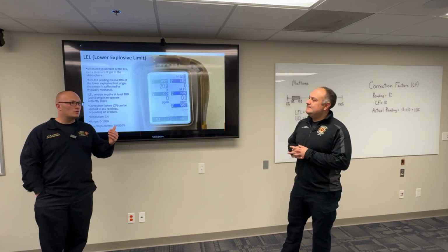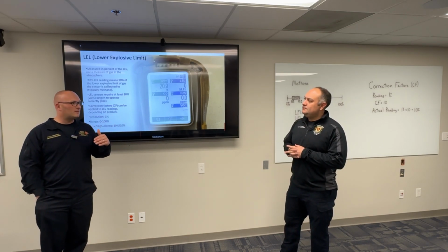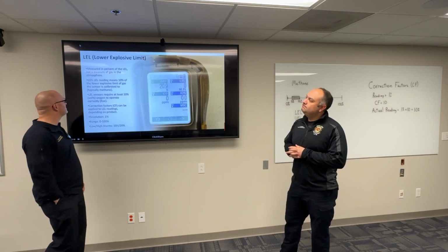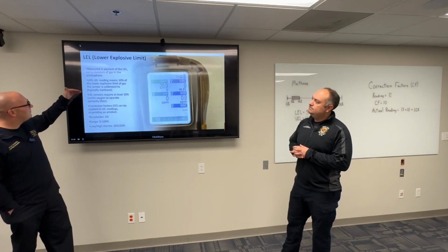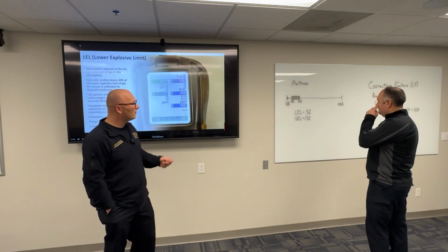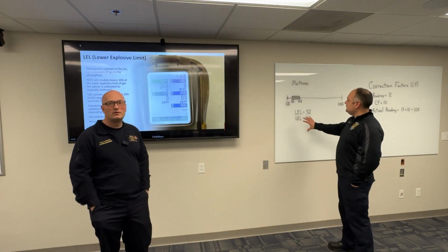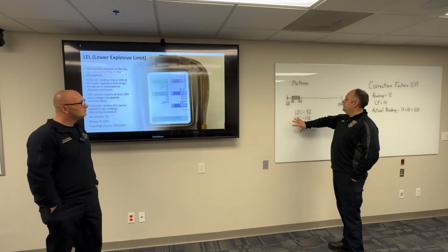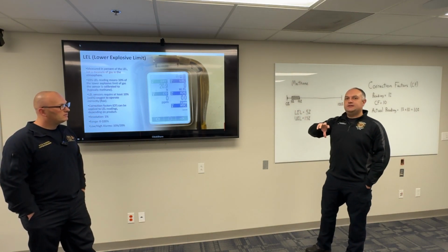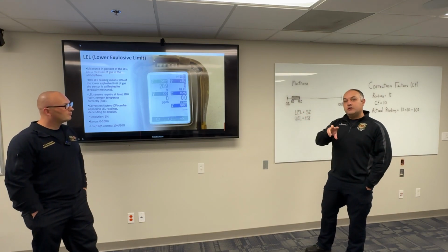And then when Spire shows up, their meters read differently than ours do. So that's a big thing to remember whenever we're diving into this stuff. So the 10% of the LEL reading, we've got listed over here. We can explain and break it down a little bit more for everybody. Yeah, so we're looking at, for RAE products, and I believe MSA is the same way, but again, you have to consult your manual to check and see what your equipment reads.